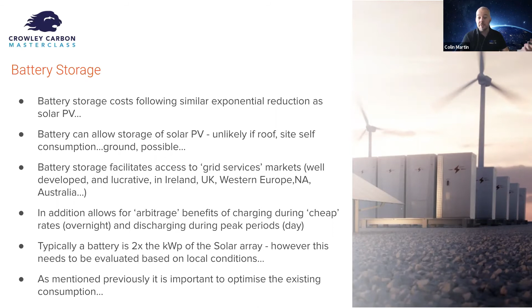You want to be optimized for high power applications. Your industrial sites, you have industrial requirements. You're not wanting a commercial or domestic scale battery. You want it to be able to deliver 400, 420 volts, whatever the voltage is. You want to deliver at the hertz, and you want that instantaneous power available very quickly. That's why we're saying the response time should be 20 milliseconds or less. So if you have a 2 megawatt battery, it comes up and is available within 20 milliseconds at 2 megawatts, or whatever your site requirement is at that point in time.